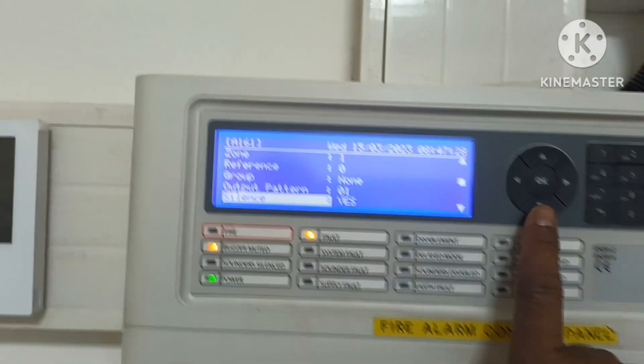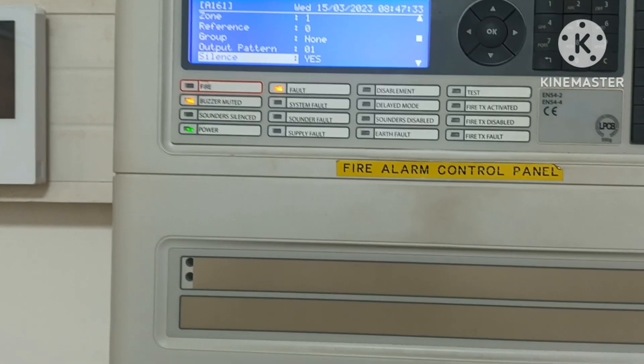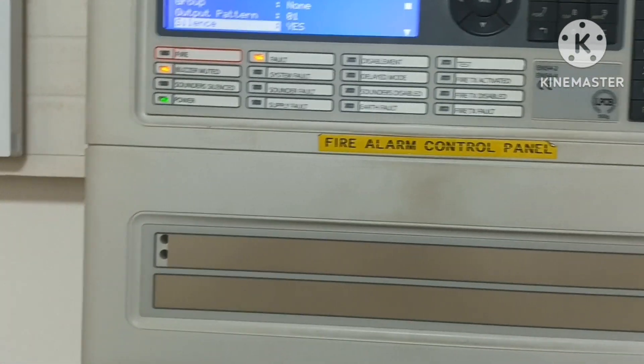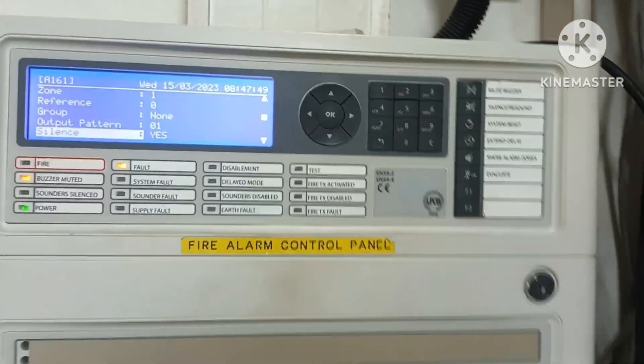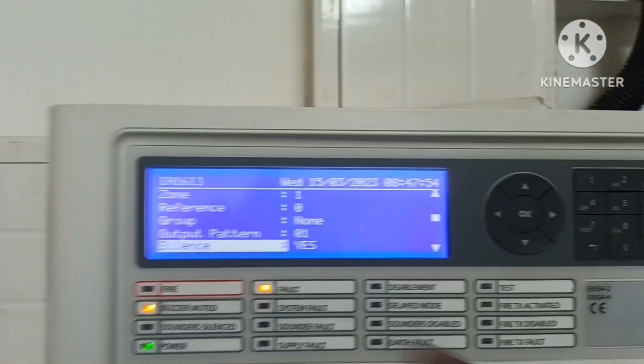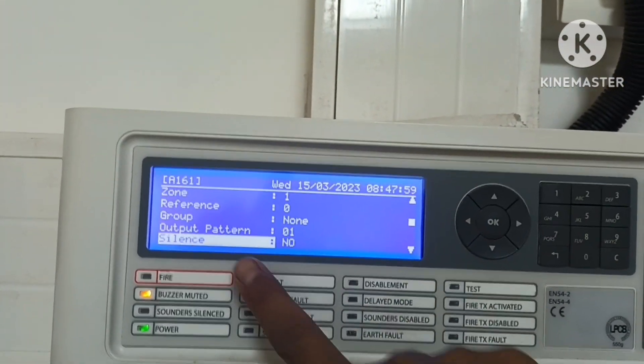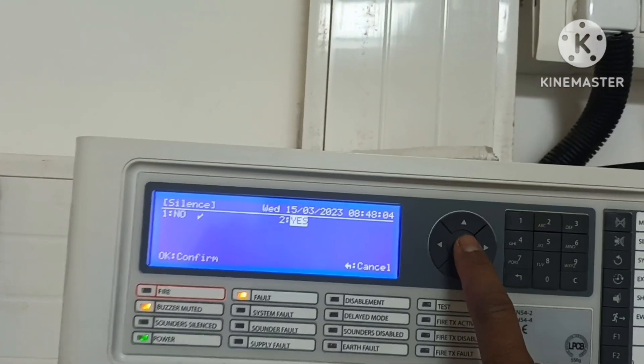If you are using this control module for sirens or hooters, you have to set Silence to Yes. When we installed the relay module and connected the hooter, the hooter was working on alarm but it was not silenced when we pressed Silence. The panel itself silenced but the hooter connected to the control relay module was not silencing because Silence was set to No.